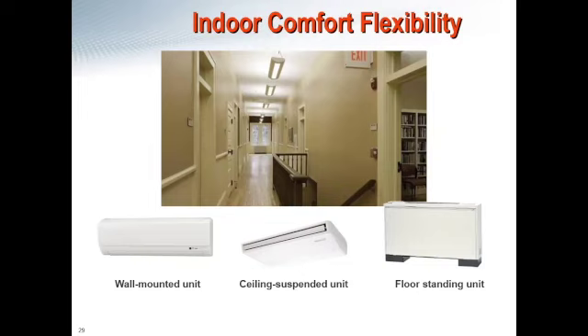Thirdly, we have the floor standing unit. This is really a great plug and play replacement for anywhere that would have a traditional floor standing 4-pipe hydronic heat pump. Most of the retrofits we do on hydronic systems, we see a lot of these floor standing units, typically in institutional buildings, schools, hospitals, things of that nature. These are a great plug and play replacement because they're built to almost the exact same specifications and size as a lot of traditional hydronic system indoor units would be.